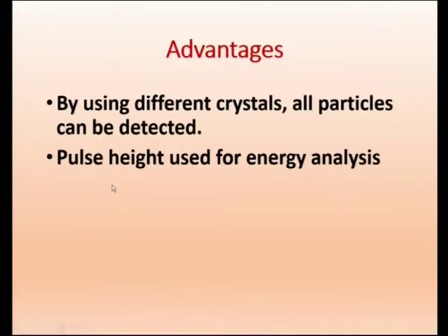Now if you change the scintillator, it can be used for any type of detection. It will be based only on the selection of crystals. The pulse height is used for energy analysis. So the height of the pulses is known, therefore we can analyze the energy. What is the energy of the particle?